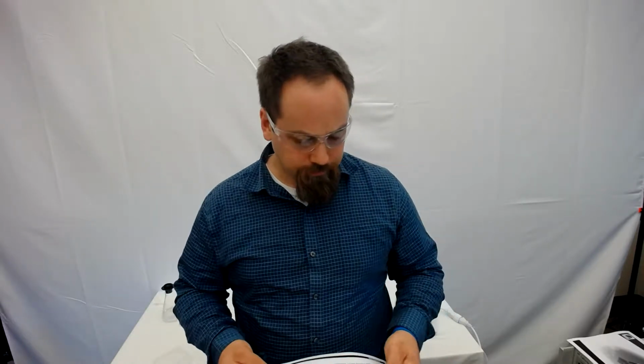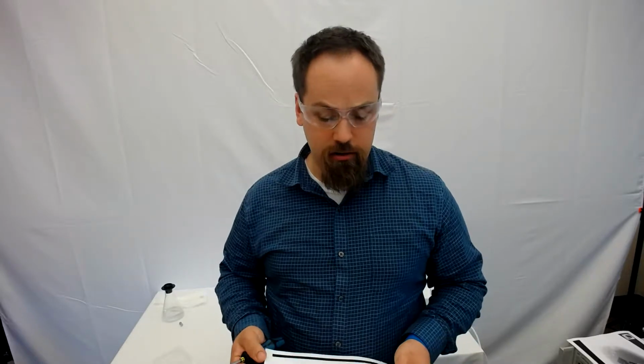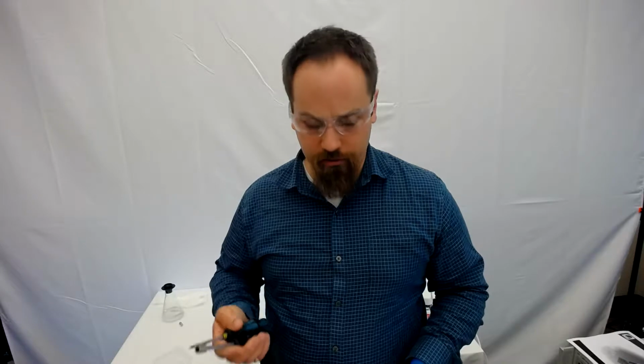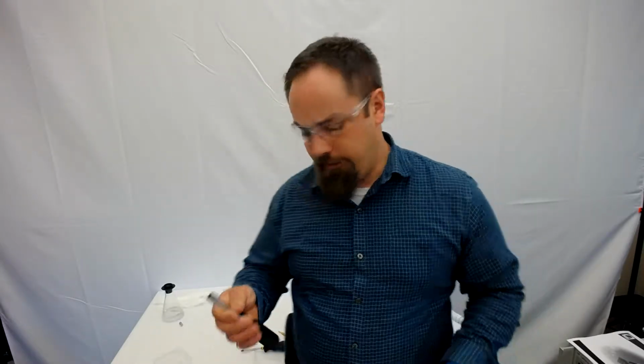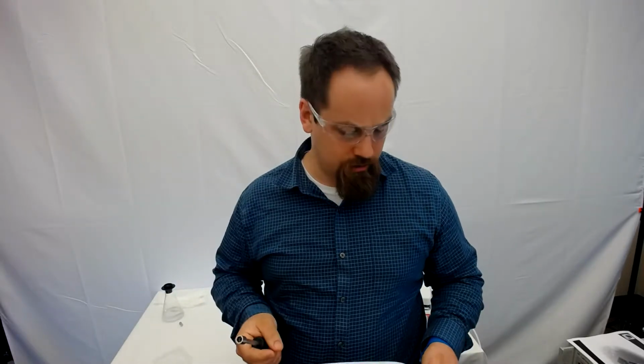So some of the tools you're going to need, we already talked about the wrist strap, and a 4 inch-pound manual torque driver. Today we're going to represent that with some hand tools. We are not going to go into exact torques, but as you're putting this back together, it is very important to torque the unit to the correct amount. All our torques that we do here at this facility are in English, but it's an easy conversion to metric torque as well. So we're going to use a 4 inch-pound manual torque driver generally for this unit. We do have an 11/32 nut driver that you will need for this unit.